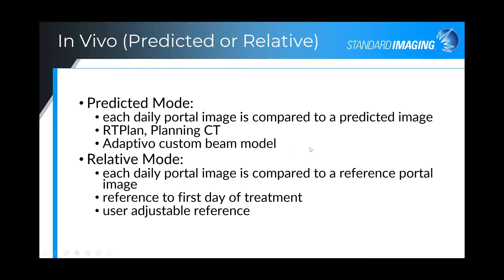The measurements for the beam model are different than what you would enter into your treatment planning system, and it takes one to two hours to acquire this data set, but model generation is very quick. In relative mode, each daily portal image is compared to a reference portal — typically the first day of treatment. If there is an alignment issue on the first day, the user can adjust the reference to any other acquired portal image.